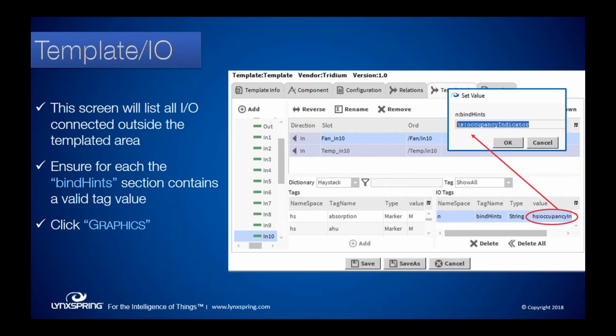If you have something that's an output, this is my schedule, and it's going to output to all of these other folders. It will also bring that in here. You'll add your tags of what that may be. So maybe my schedule is controlling fans. So I would put something like HS:fan to bring up a list of fans. Because it's an output, when I get that prompt, it's going to let me select multiple fans, that this can be the input for that fan or the output from this item to that fan. We'll see that in a little bit when we look at the deploy.